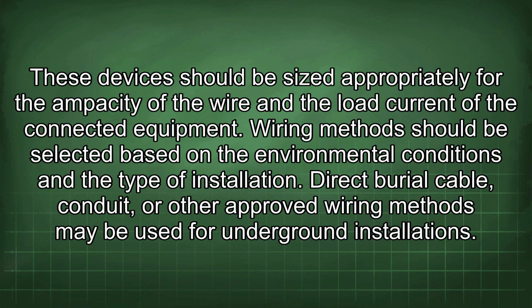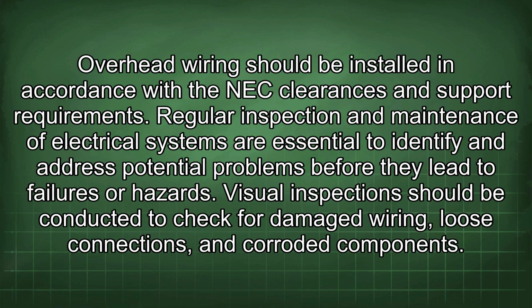Direct burial cable, conduit, or other approved wiring methods may be used for underground installations. Overhead wiring should be installed in accordance with the NEC clearances and support requirements. Regular inspection and maintenance of electrical systems are essential to identify and address potential problems before they lead to failures or hazards.